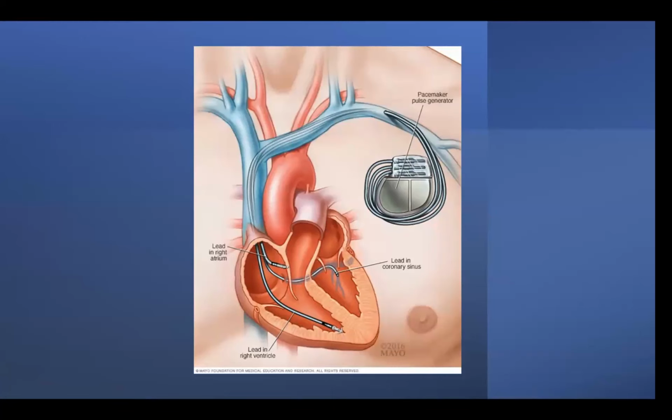Jared, have you ever had that? No, I haven't heard of that one, mate. I've heard of physicians talking about it, or even touching the metal instrument within the pocket to the can itself, and you'll be able to maintain capture. But I don't think it's the best solution. It's always better to have a temporary pacer if you can, or have very quick hands, I guess, putting the device in and out of the pocket for unipolar. But unipolar can also be a good solution when you're trying to capture.